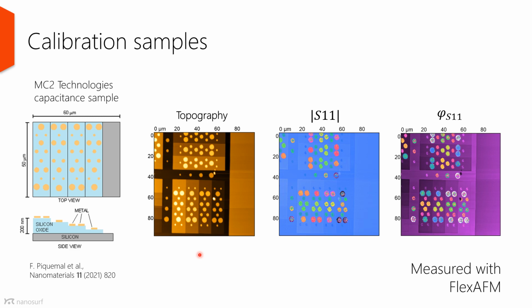In our measurements, you can see a clear contrast between the terraces and the dots. In fact, these silicon oxide structures are often used to measure the device performance because they are of known thickness, and it's easy to recalculate the signal into the change of the capacitance. And from this, you can determine the capacitance noise of the instrument.